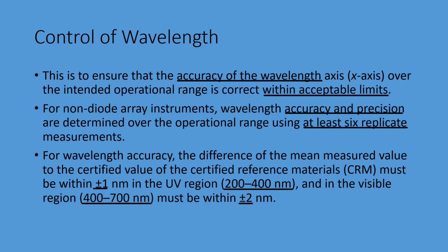So the wavelength accuracy must be within 1 nm in the 200 to 400 range and within 2 nm in the 400 to 700 range.